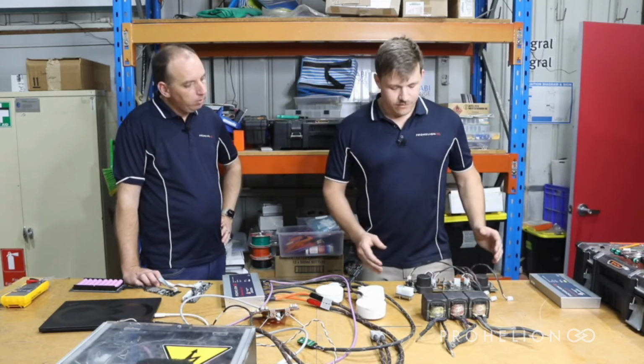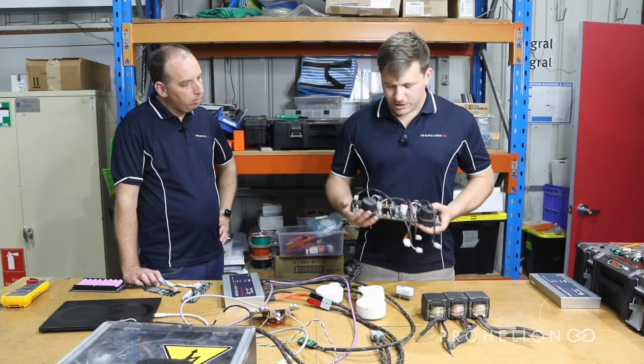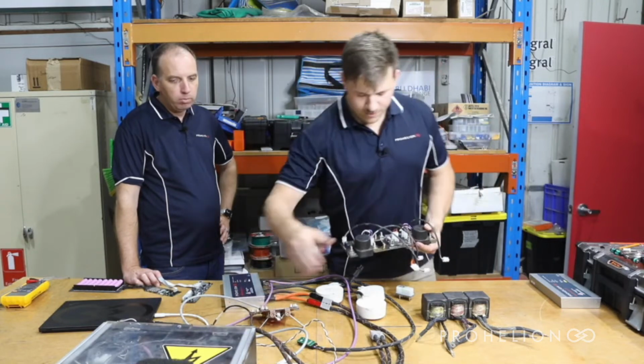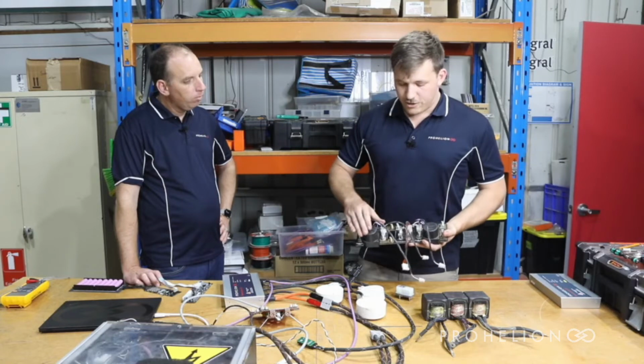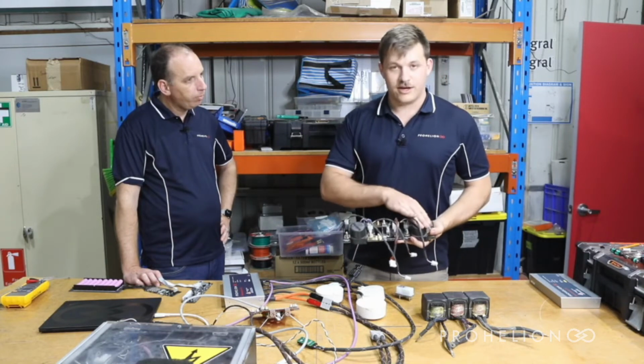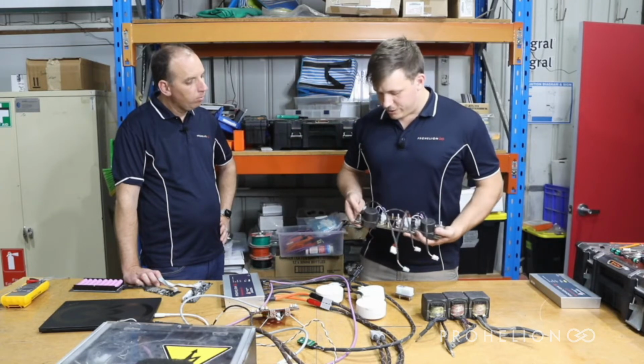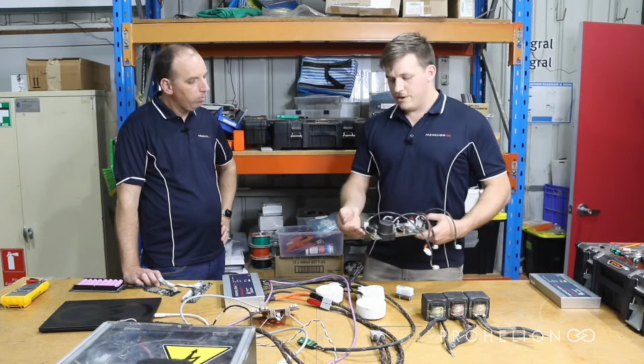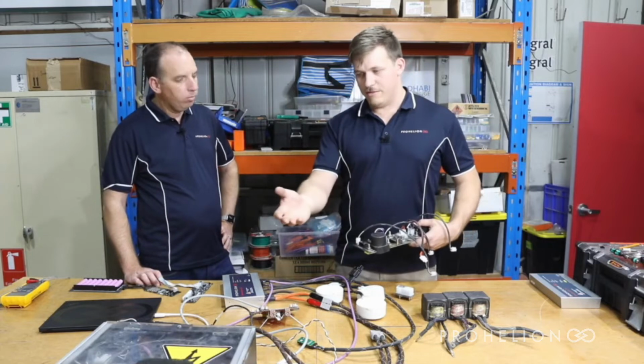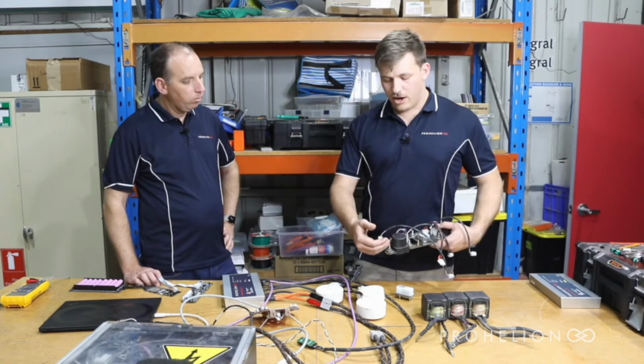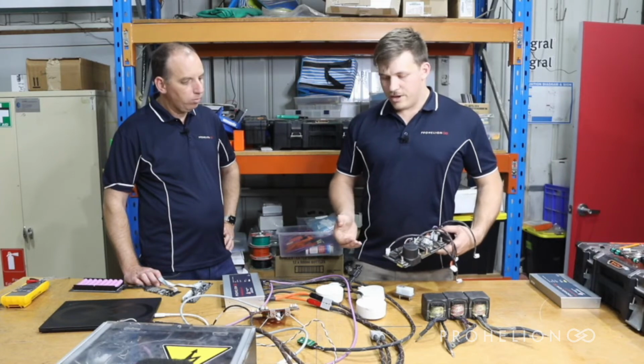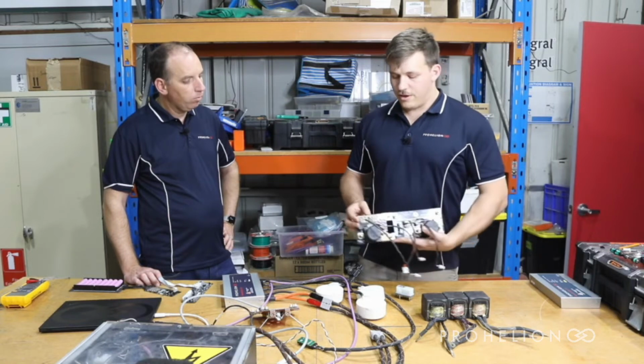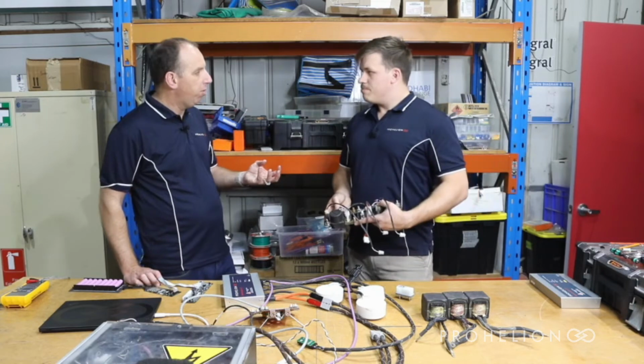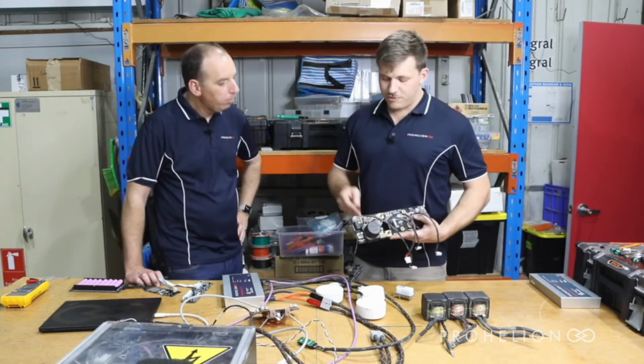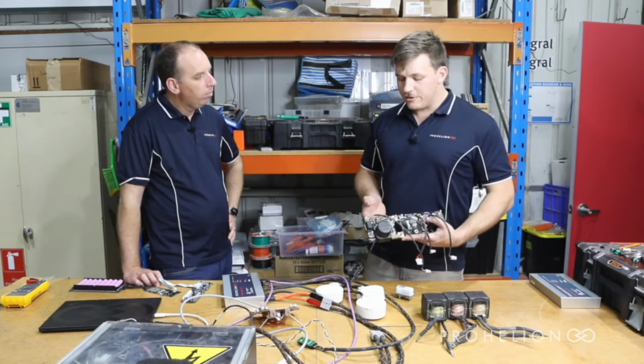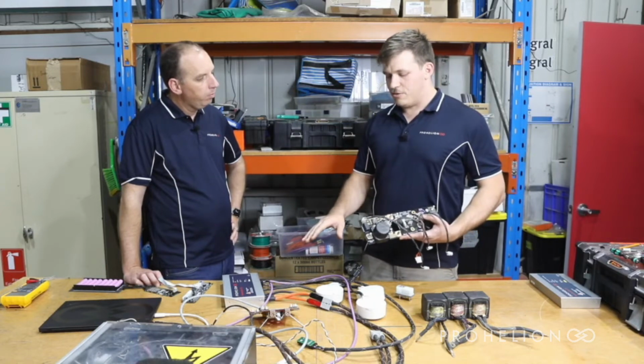Okay. So I've got here an example of a contactor high voltage distribution block that's in this system here. Just to quickly run over it, we've got the two main contactors that control the positive and the negative output of the pack. And we've also got on the side here the precharge relay. This relay, when controlled by the BMU within the battery, will switch the internal high voltage to the output high voltage positive through a power resistor. That's the only reason that resistor's there, basically for this precharge function. Exactly. Yeah. So this precharge resistor just acts as a limiter for the inrush current and allows the voltage on the output capacitance to come up in a controlled manner.